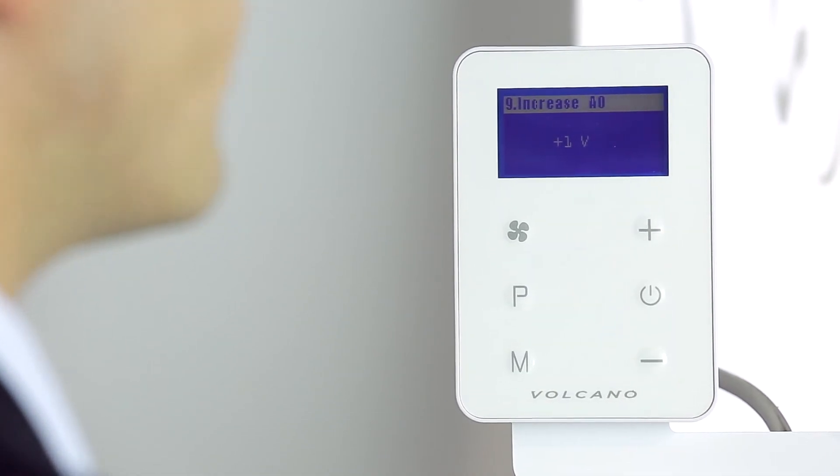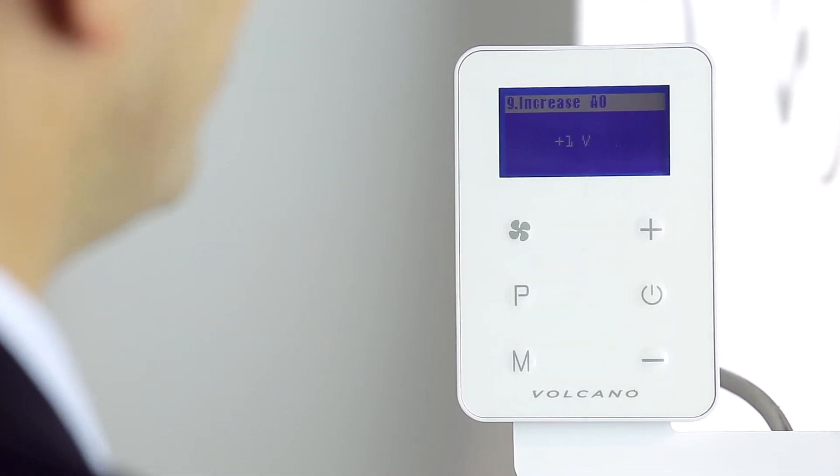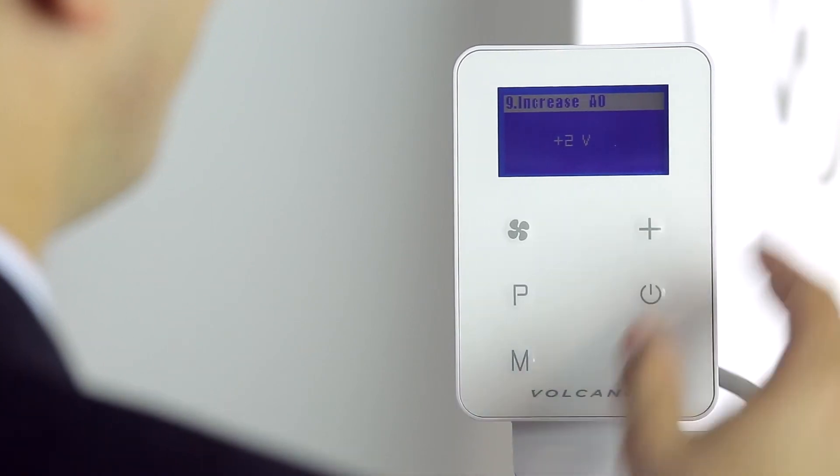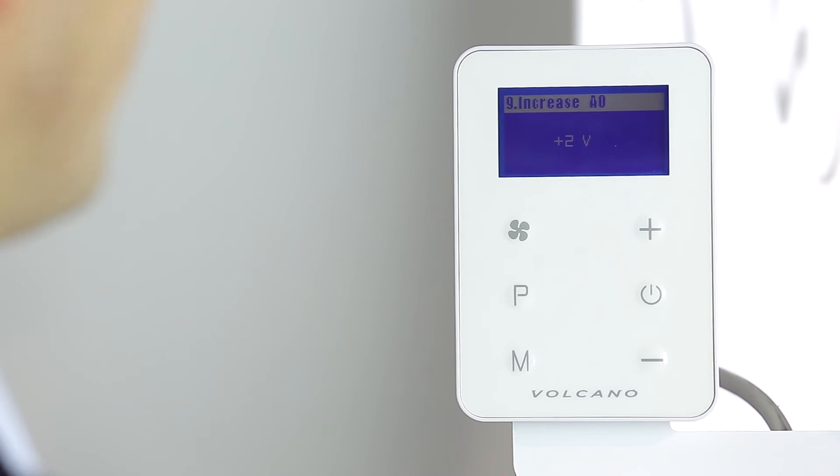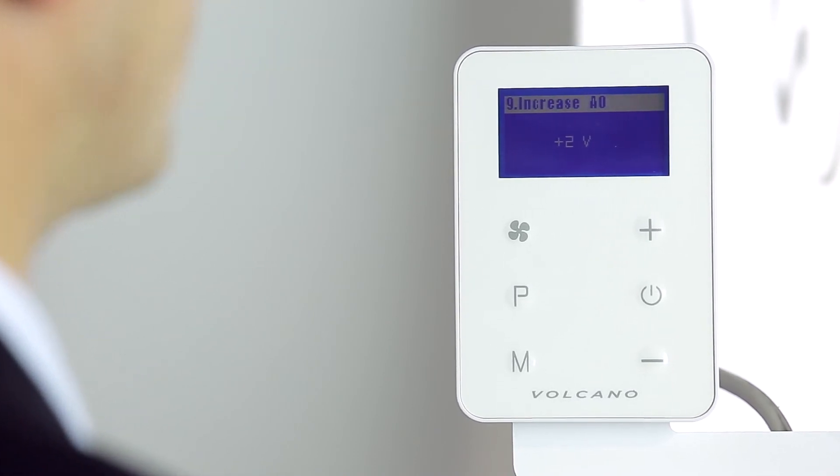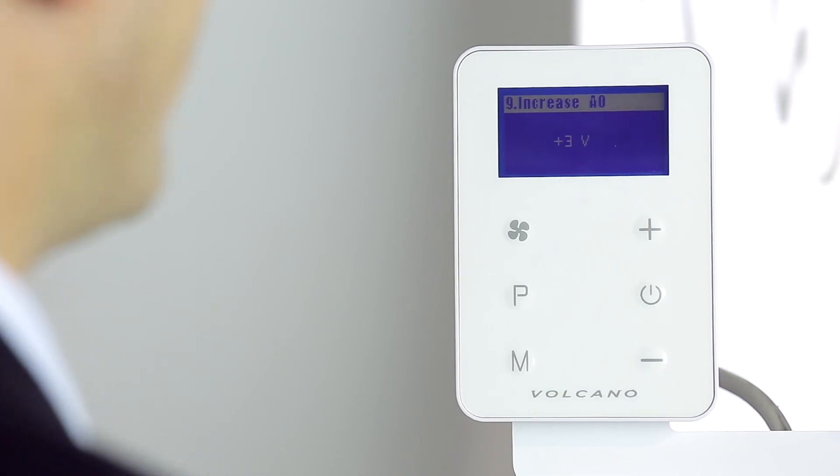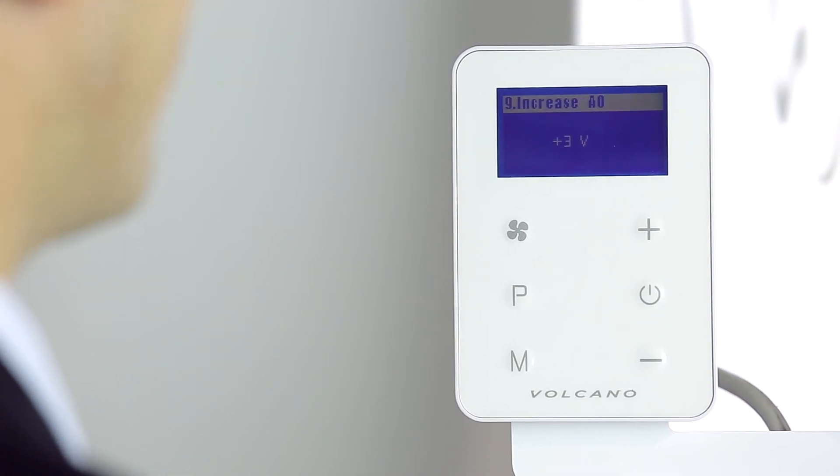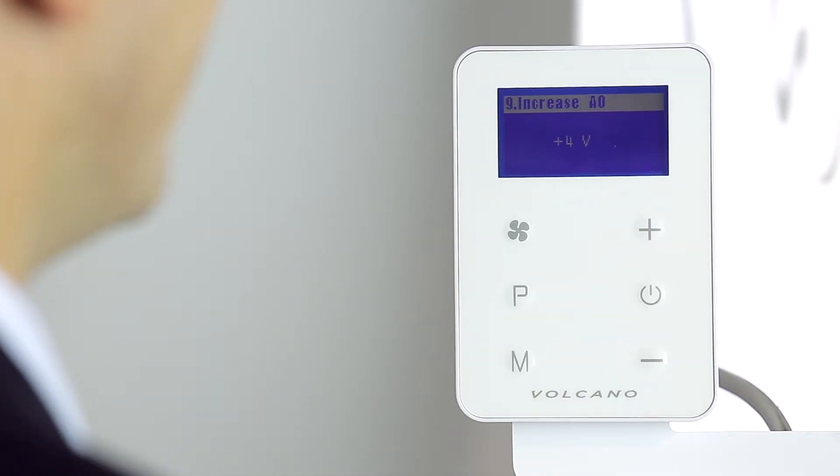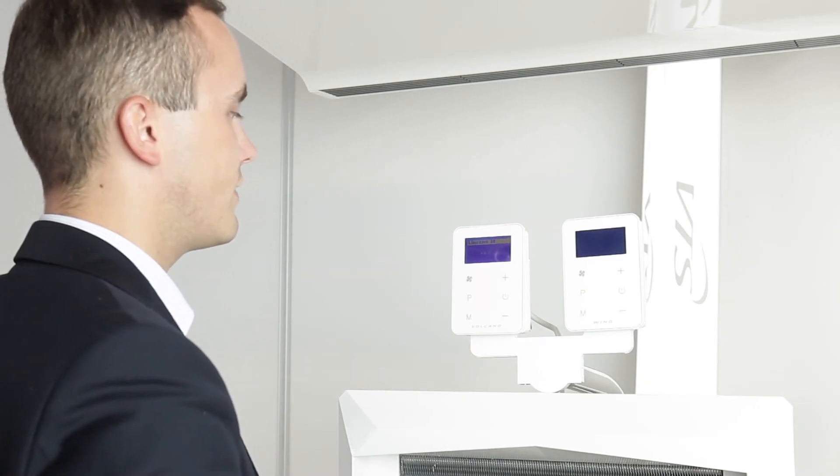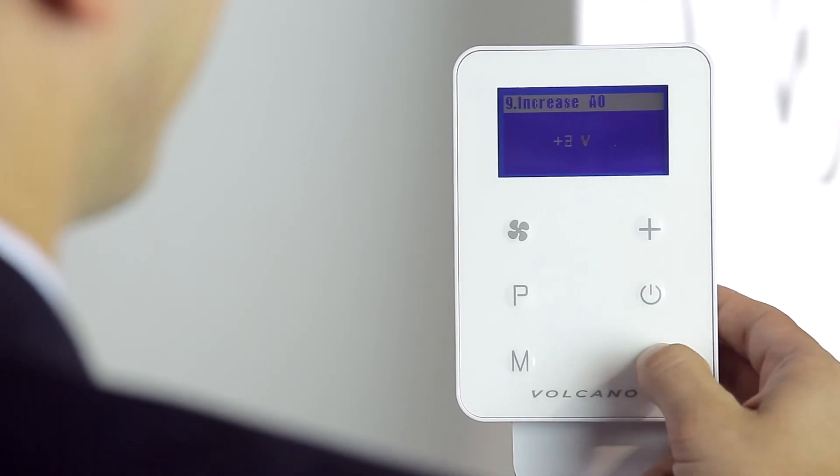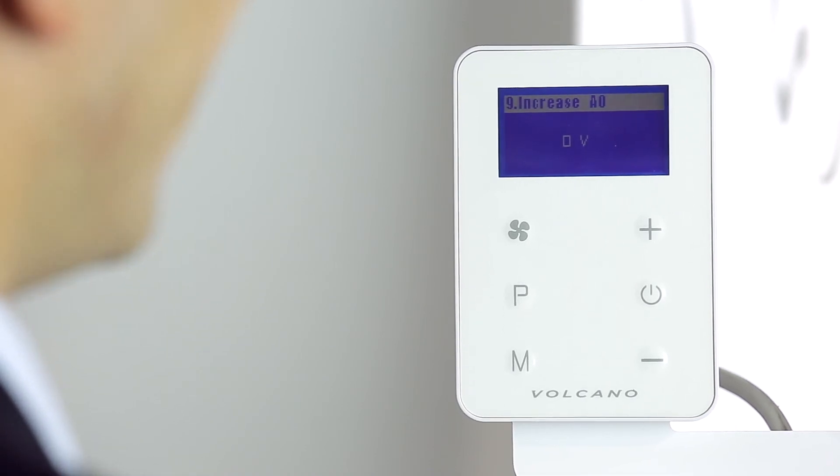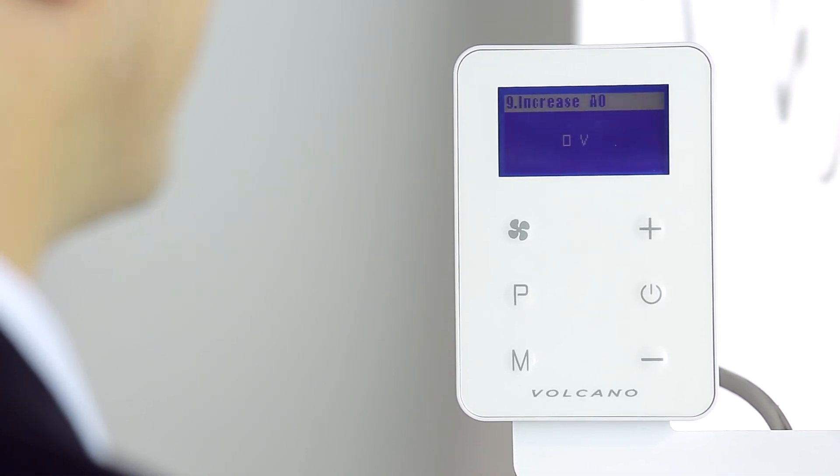We suggest plus one volts for objects with a surface area of 150 to 250 meters squared, plus two for objects with a surface area of 250 to 400 meters squared, plus three for objects of surface 400 to 600 meters squared, plus four volts for objects larger than 600 meters squared. Zero volts is the default setting, which does not increase the output signal of our controller.